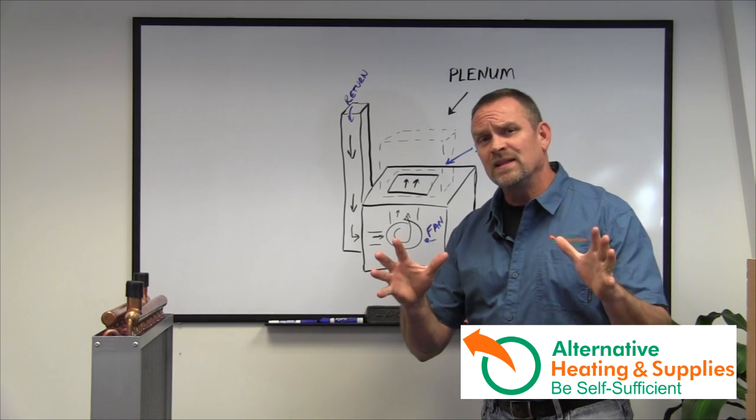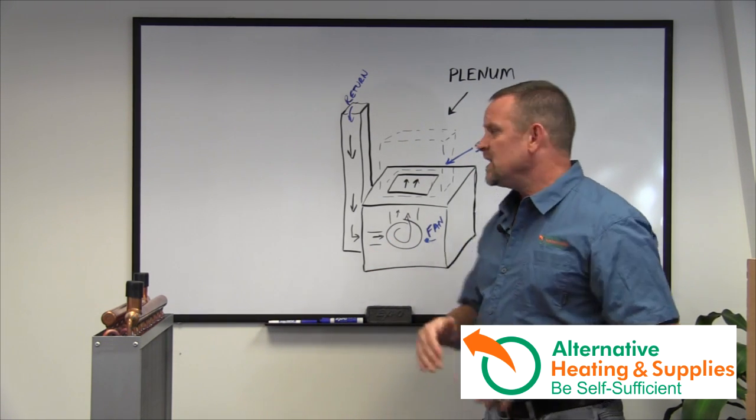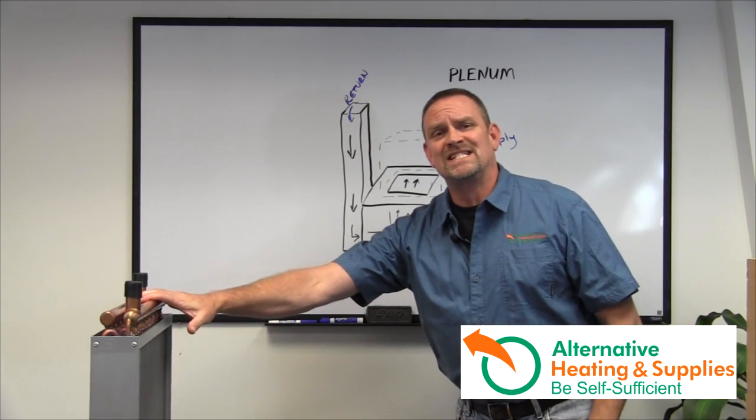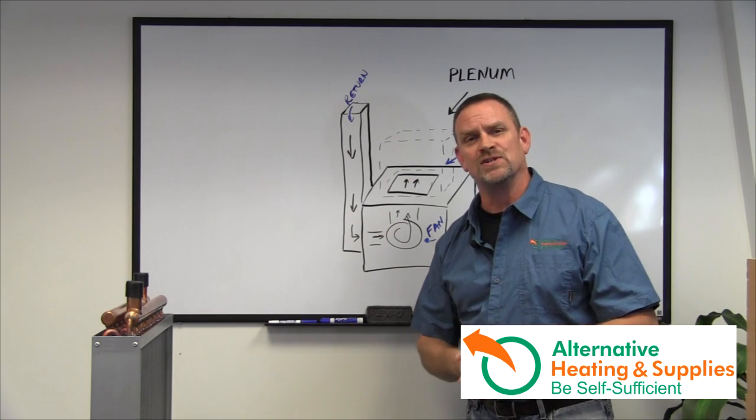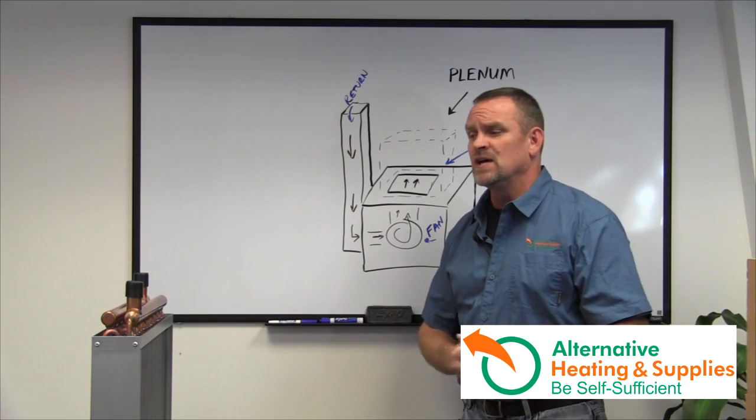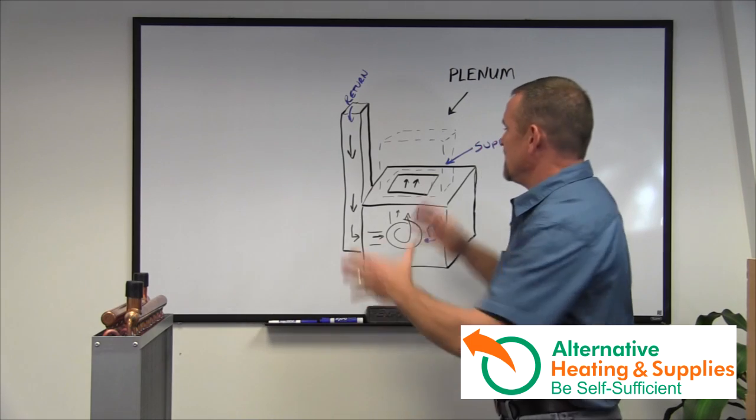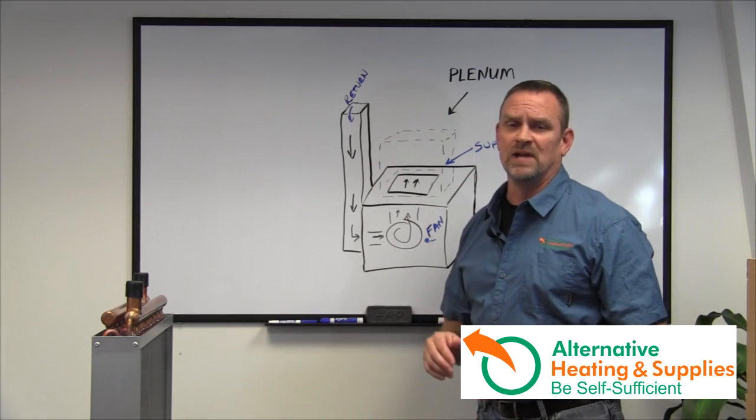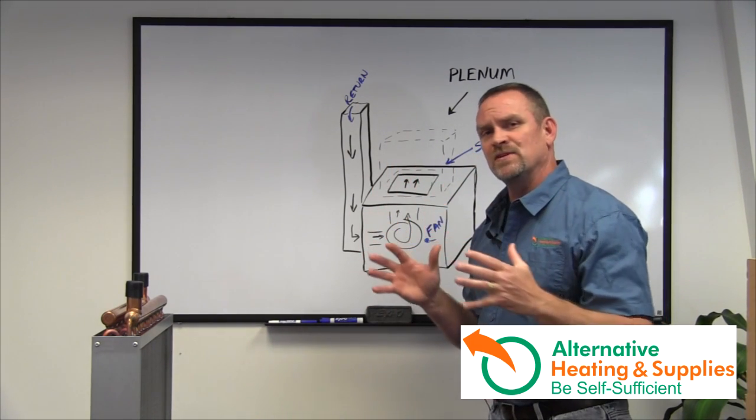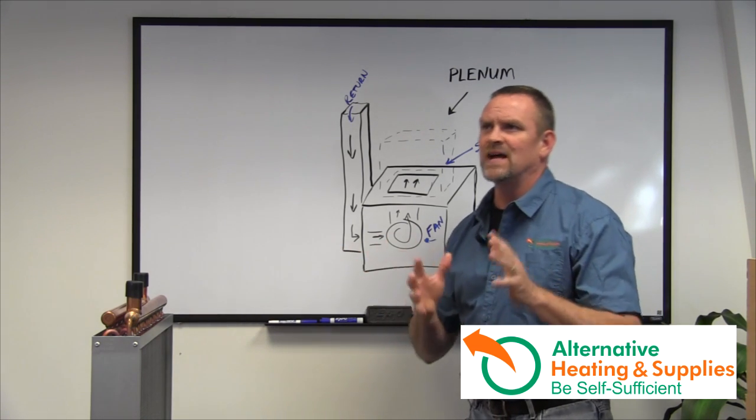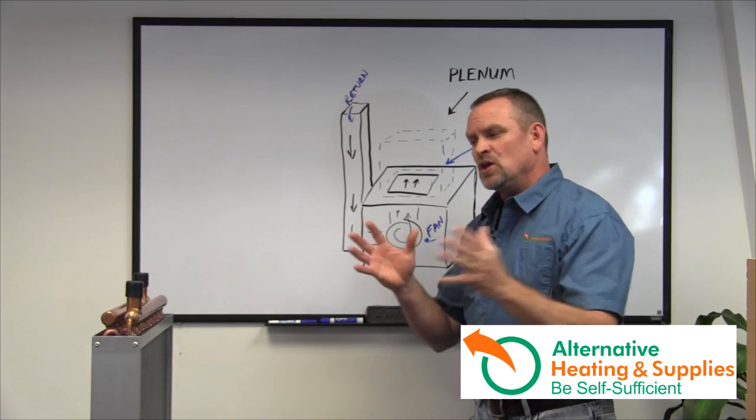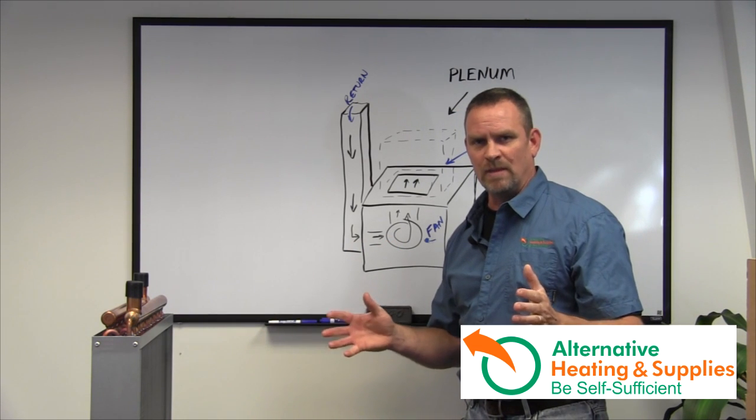And then one more thing that a lot of people ask me about is, does this generate resistance on the fan? Does that slow down the airflow through my house? The answer to that question is simply, yes, it sure does. So you want to find a heat exchanger that is going to maximize the size of your plenum so you get the least amount of resistance. Now, if you 99% of the time, you do not have a resistance problem once you install them.